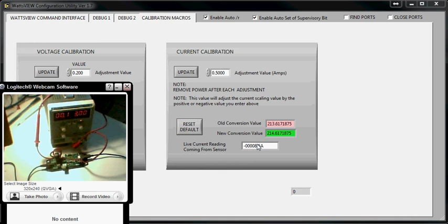We'll go over to the calibration macros where it says current calibration, and we're off by about 0.5, so we're going to put 0.5 here and then hit update. For this to take effect, we have to unplug the sensor power, unplug it and plug it back in, and that'll reset the microprocessor. And then we're going to take a look at the data coming in.